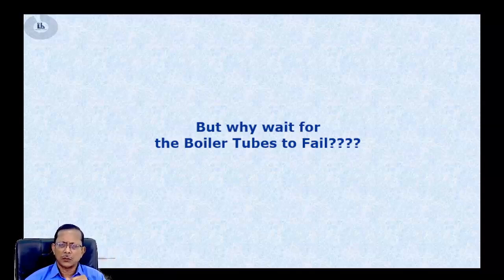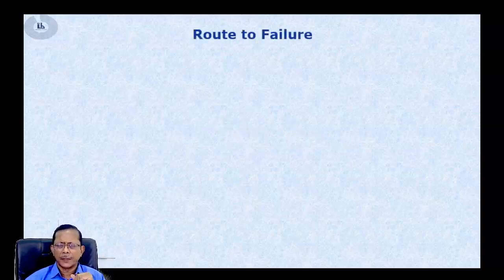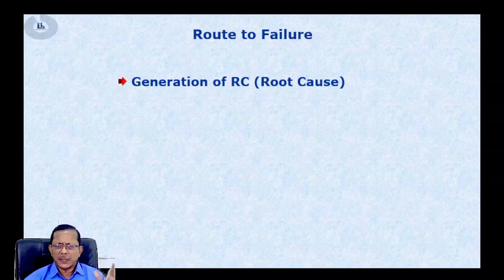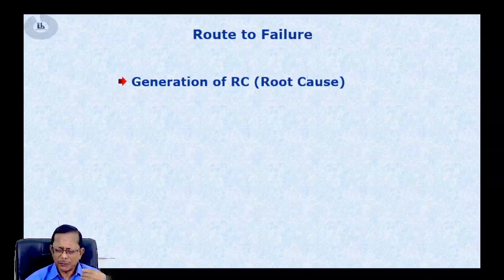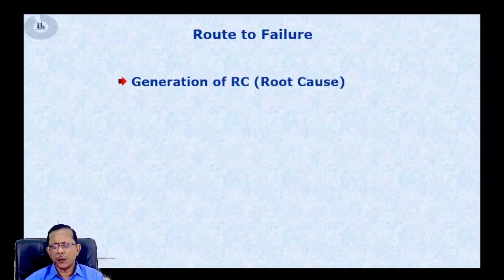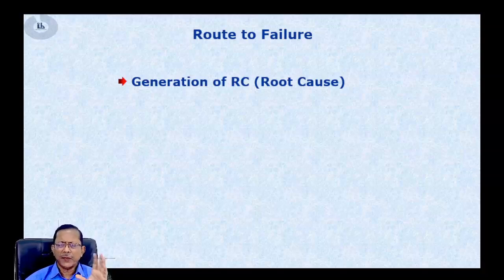From failure to root cause — what are the roots? The root cause is basically a mistake. A mistake that can happen in design — for example, certain superheater coils having more area than desired and picking up more heat. It can happen during erection, and it can definitely happen during operation, where certain operating conditions are not maintained properly, creating a situation that leads to failure.